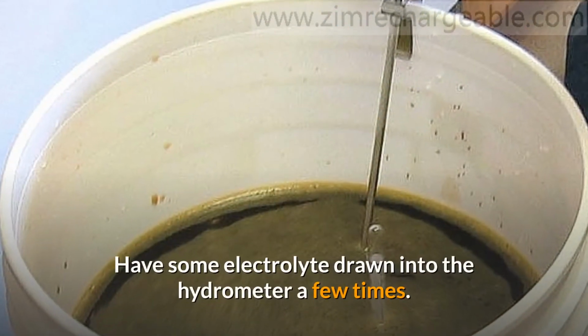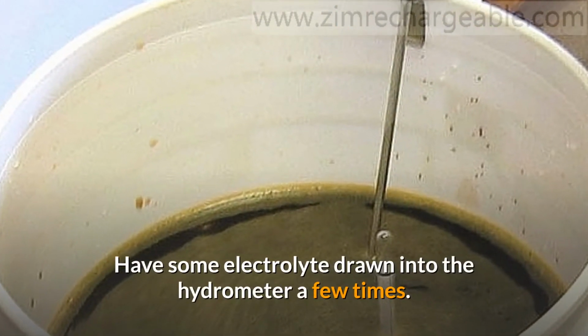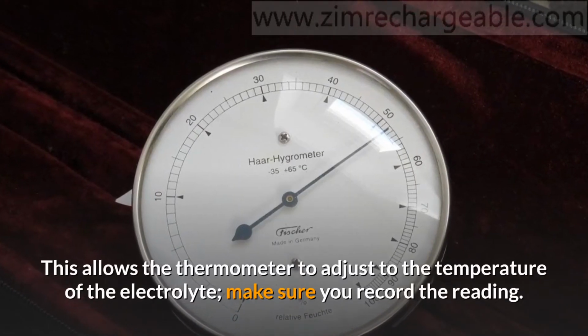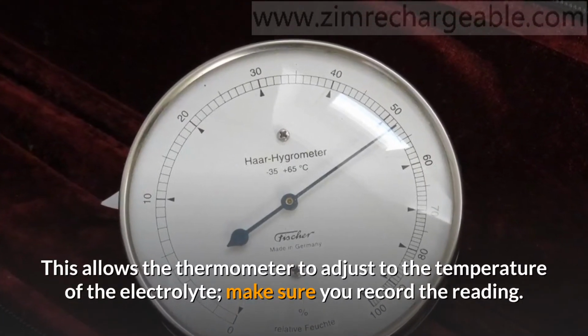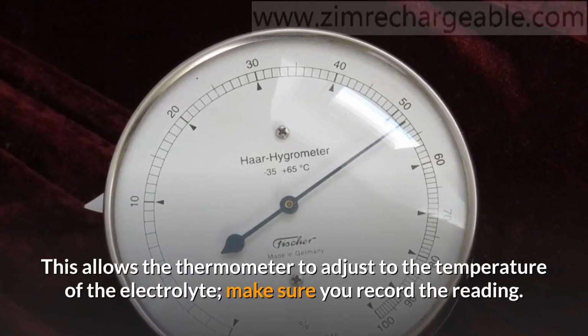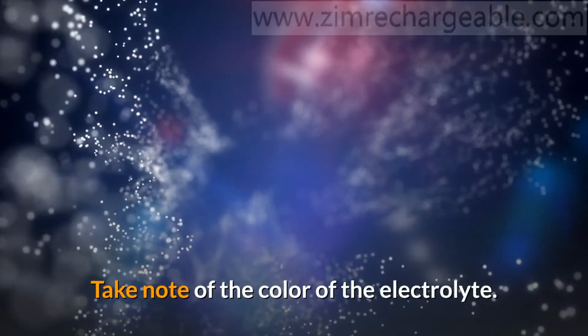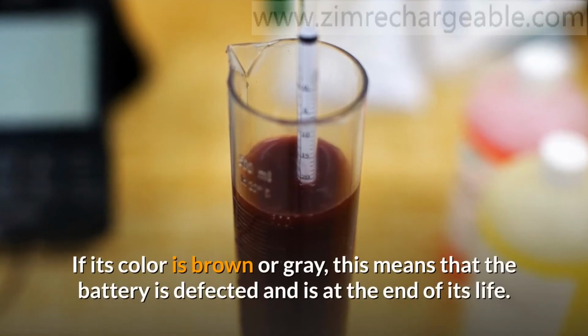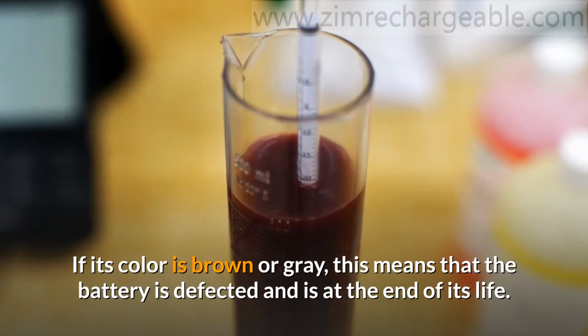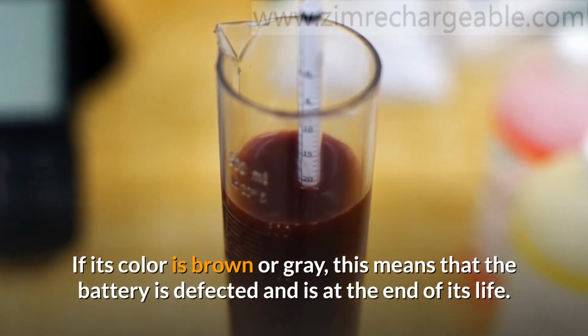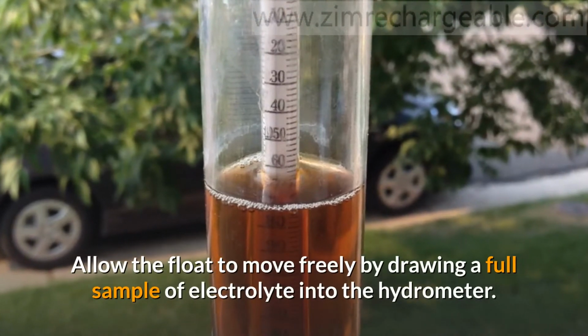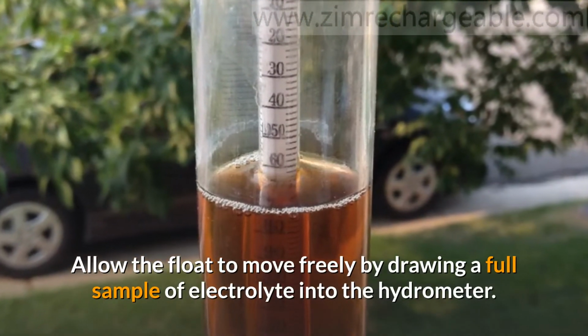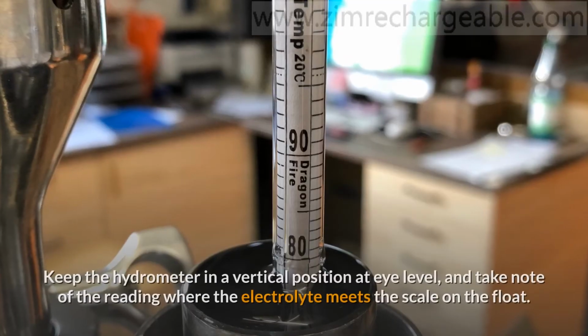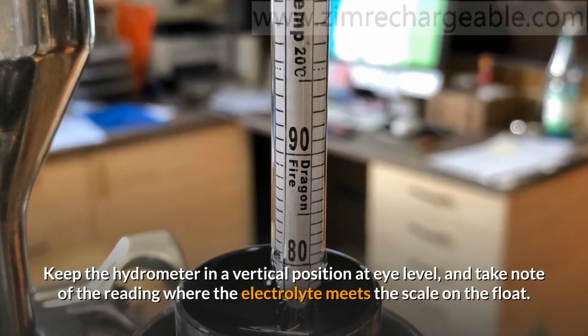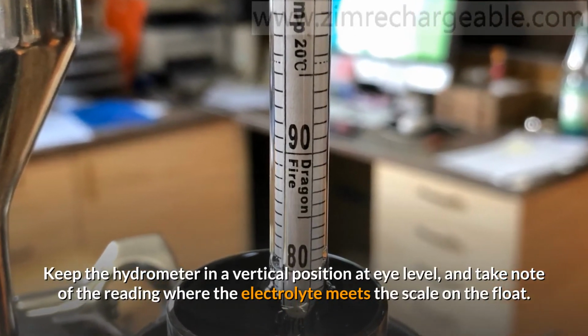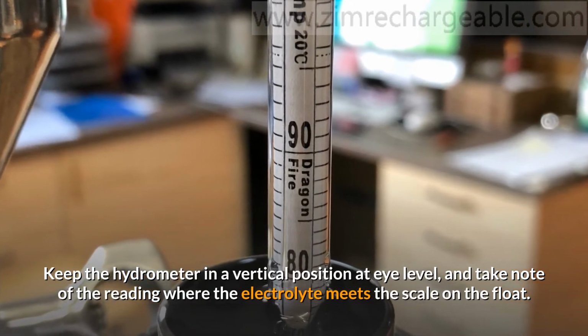Have some electrolyte drawn into the hydrometer a few times. This allows the thermometer to adjust to the temperature of the electrolyte. Make sure you record the reading. Take note of the color of the electrolyte. If its color is brown or gray, this means that the battery is defective and is at the end of its life. Allow the float to move freely by drawing a full sample of electrolyte into the hydrometer. Keep the hydrometer in a vertical position at eye level, and take note of the reading where the electrolyte meets the scale on the float.